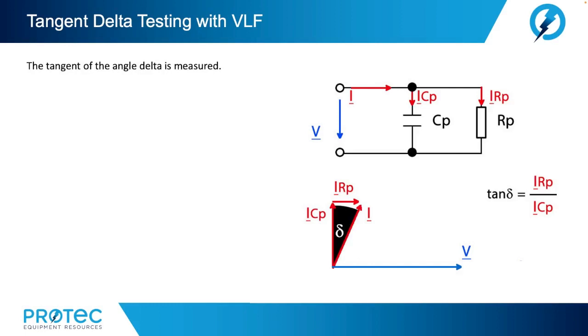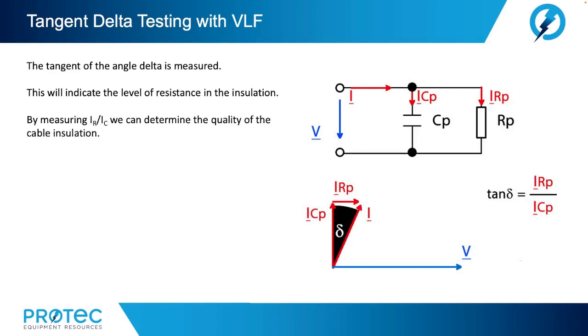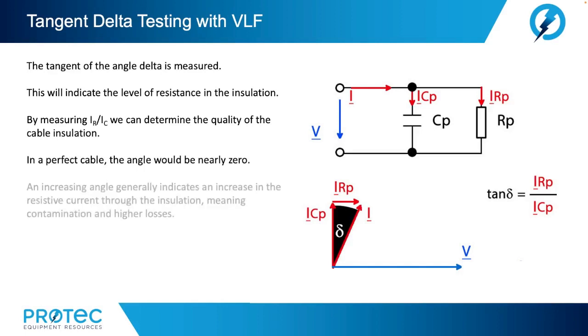The tangent of the angle delta is measured. This will indicate the level of resistance in the insulation. By measuring the resistive current divided by the capacitive current, we could determine the quality of the cable insulation. In a perfect cable, the angle would be nearly zero. An increasing angle generally indicates an increase in the resistive current through the insulation, meaning contamination and higher dielectric losses.